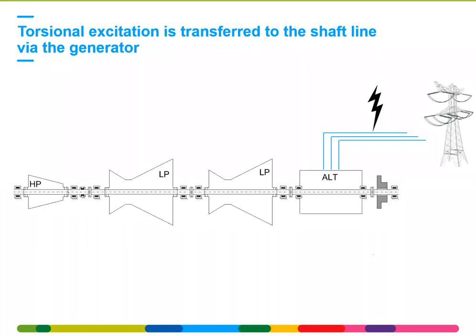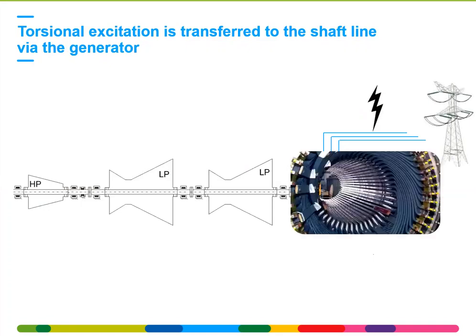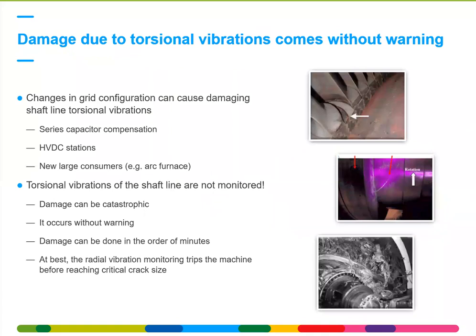Well, your mechanical shaft line is connected with the electrical grid by means of the generator. So the electromagnetic field in between the rotor and the stator actually couples the mechanical part, being the shaft line, to the electrical part, being the grid. And so any perturbation on the grid will be felt mechanically in the shaft line. So you have a true coupling electrically, mechanically.